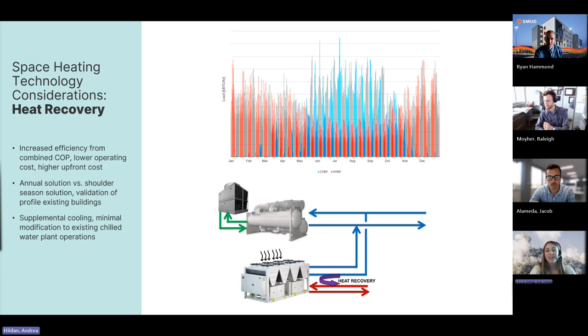specifically because there's a lot of challenges with these existing buildings verifying this annual profile, because a lot of these buildings are aged and there's no monitoring systems currently in place or advanced metering to help trend these systems and identify when there truly is a call for heating and cooling demands within those buildings. So a couple of methodologies that we on the Glumac team have found successful is working with ownership and the utility to procure past utility bills to help build trends beyond even a year profile, maybe dating back 2, 3, or even 5 years of data.